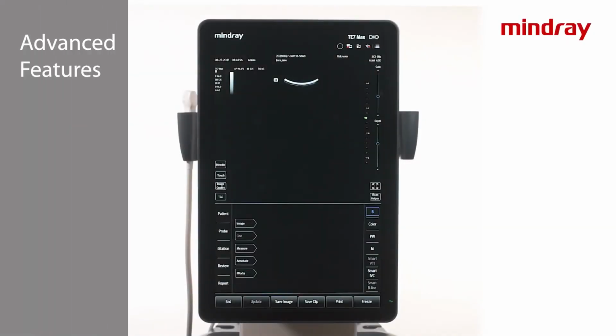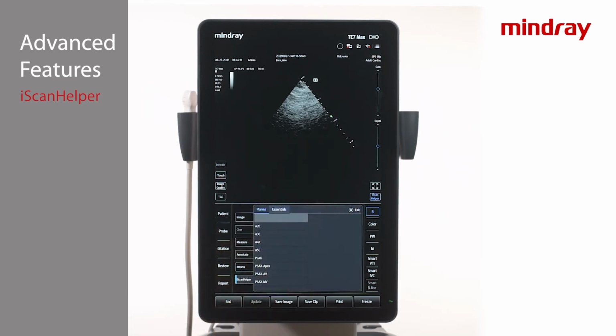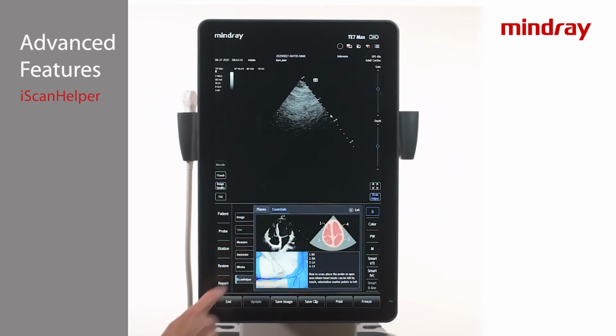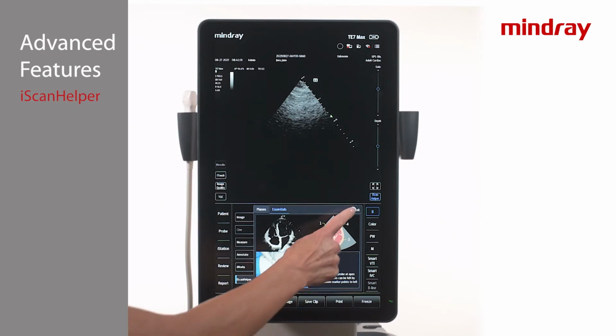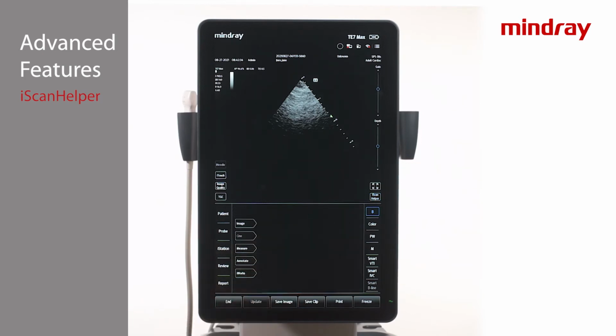iScanHelper is an educational reference tool built into the system, which provides tutorials and is exam mode specific. To initiate iScanHelper, select the desired transducer and exam mode, then tap the iScanHelper icon on the touchscreen. Select the target view and the system will display 4 different informational screens. The system will provide you with an image which portrays proper transducer placement, desired ultrasound image, a graphic pictorial, and additional scanning tips. Tap the iScanHelper icon to exit. Please note that images cannot be saved while iScanHelper is active.